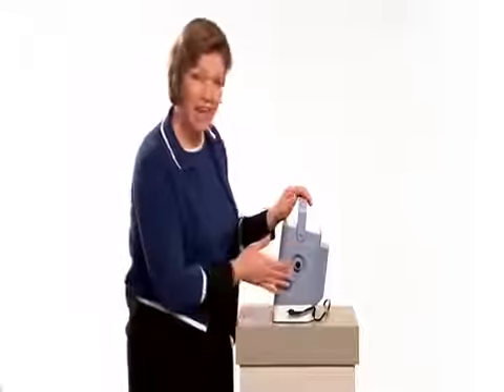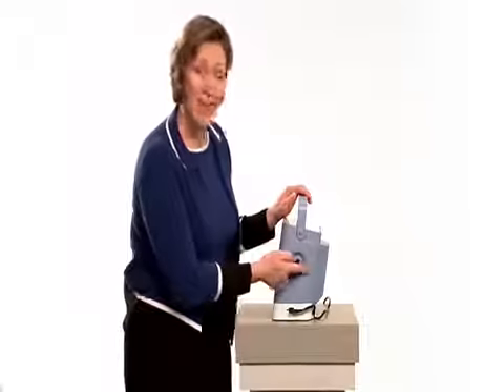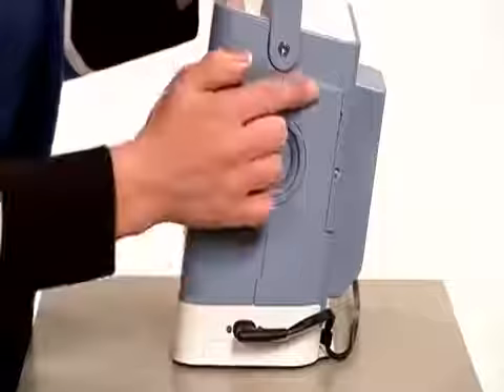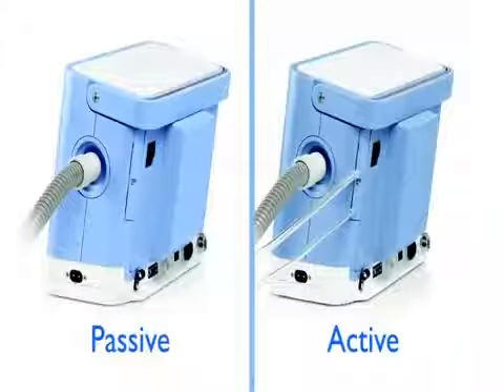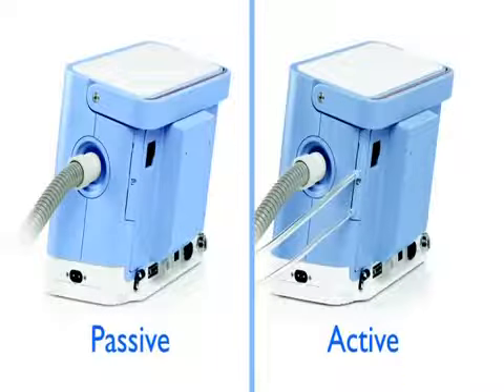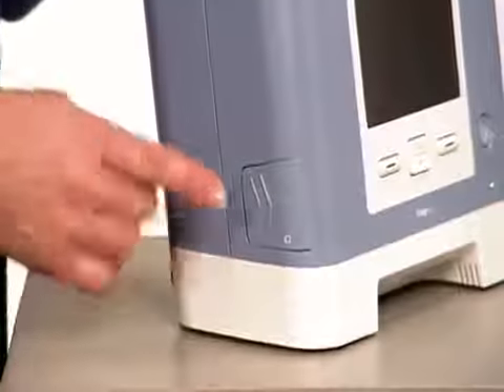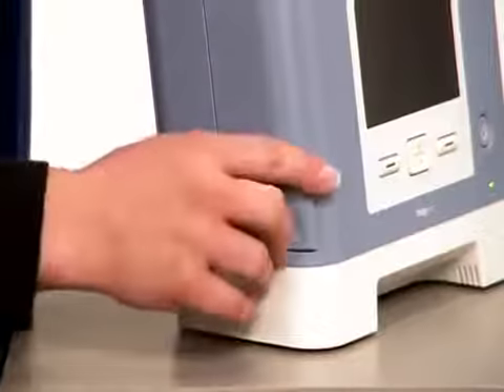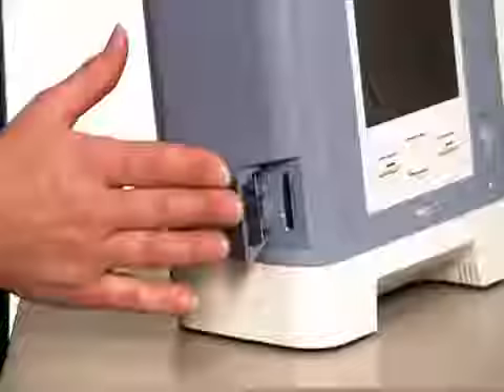The device we're looking at now is fitted with a passive exhalation porting block, which is this piece in the back. If you're using an active exhalation porting block, your device will look like this with 2 additional connection ports. Let's look at the other side of Trilogy. The slot is for a secure digital or SD data card. This is an optional card that collects ventilation data for your physician.